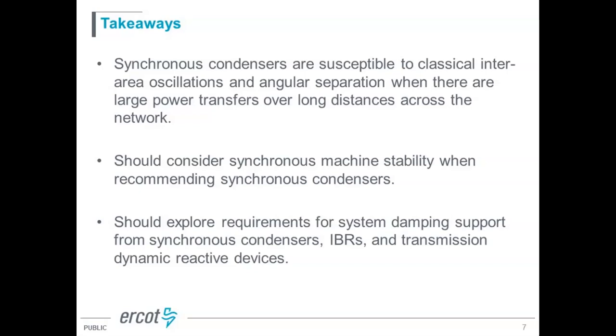So really, in the future, when we try to consider additional condenser applications to improve system stability under stress, I think a lot of synchronous machine stability related issues need to be examined, and we also need to explore how to have sufficient damping if condensers are added into an area where only inverter-based resources or FACTS devices on the transmission side provide the long-distance transfer. So that would be my summary of this one.